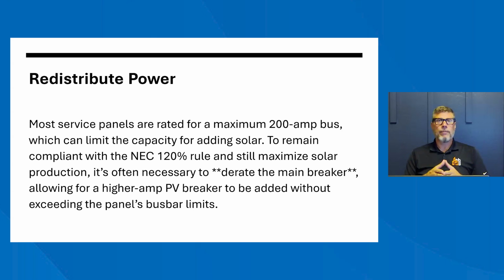It is not uncommon to go to these older systems and see a 200 amp panel, which is very common, with a 200 amp disconnect, which is very common, and have a 60 amp disconnect for your solar panel. I can almost guarantee you that when you look at it, you're going to see that main bus is going to be discolored. The reason why is because we've pumped too much power to it. It has gotten hot, maybe not too hot, but it has gotten hot and it starts to discolor. It'll turn orange, gold, purple. Once it hits purple, we've really got a problem. So that is something that you want to look for.